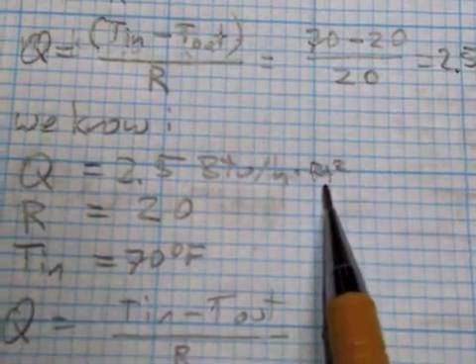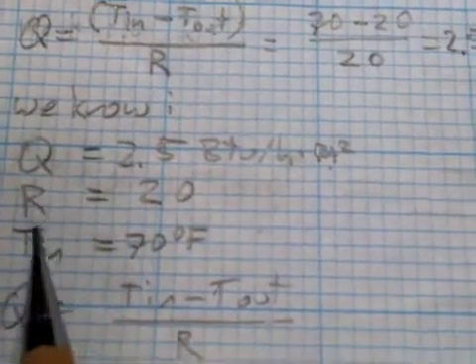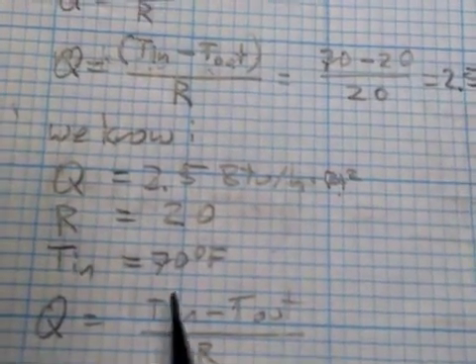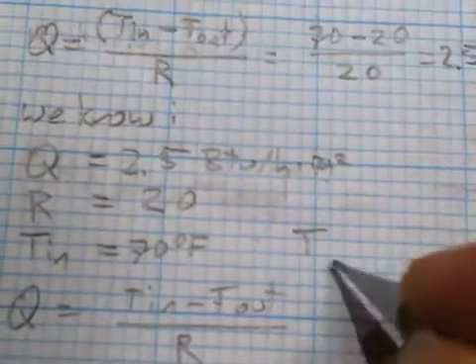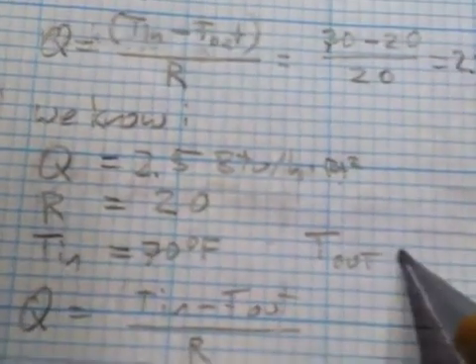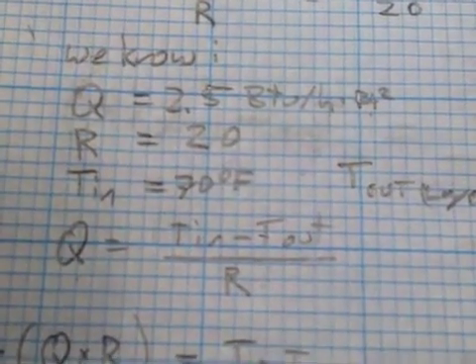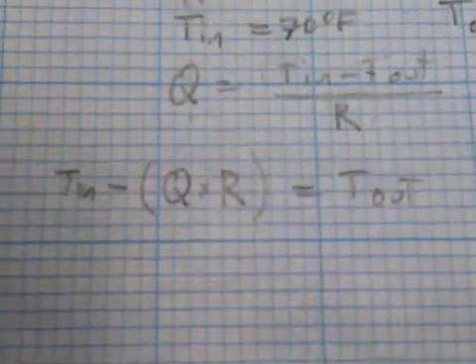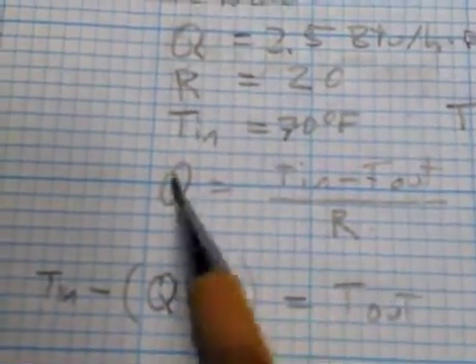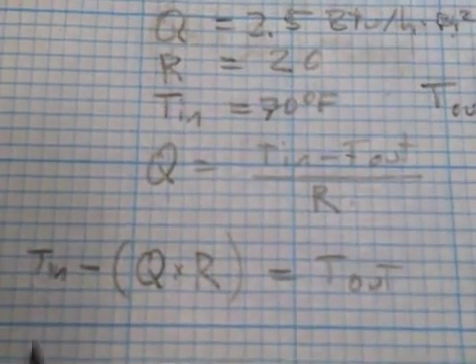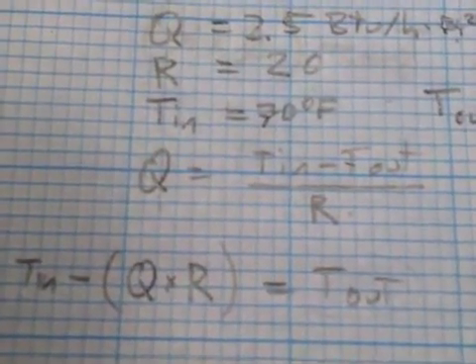So we know Q = 2.5 BTUs per hour per square foot, total R = 20, and inside temperature = 70°F. What we want is the temperature at the outside face of each layer. We use the formula Q = (T_in − T_out) / R, rearranged to T_out = T_in − (Q × R). We multiply by R to isolate it, and subtracting Q × R from the inside temperature gives the temperature at the outside of each layer. We build a table to apply this systematically.